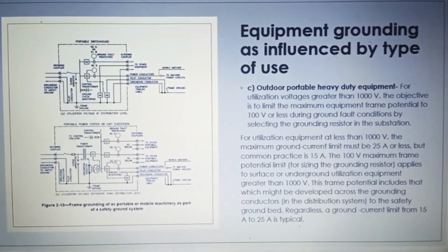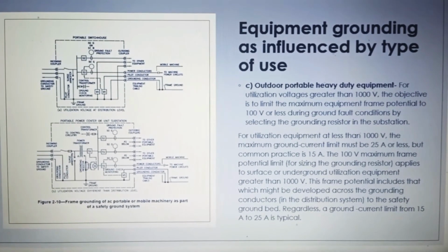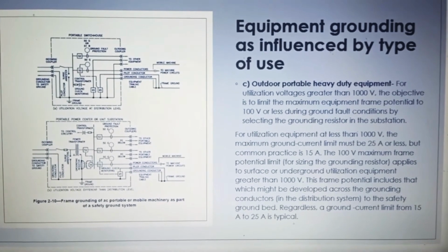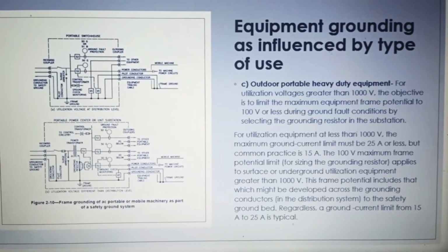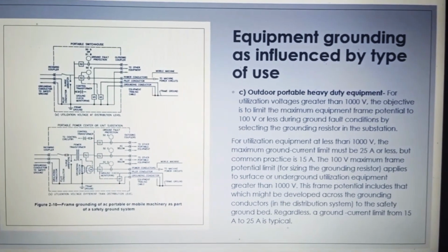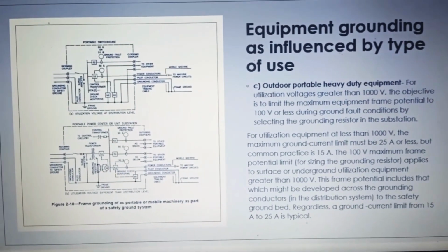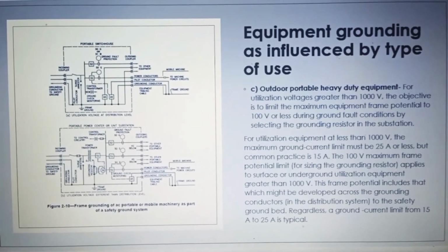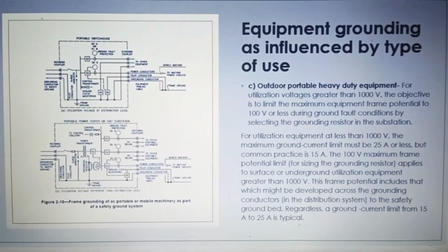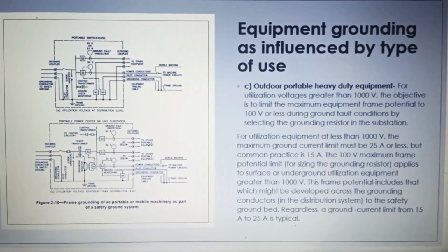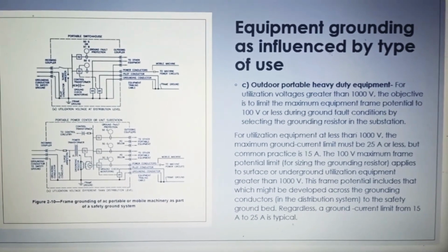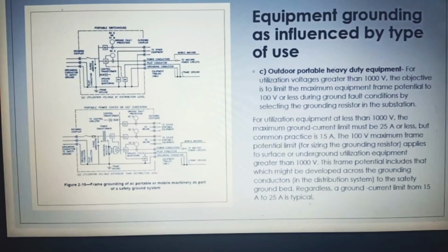Outdoor portable heavy-duty equipment. This area usually involves equipment such as power shovels, draglines, and mine installations. It presents one of the more difficult problems in avoiding dangerous electric shock voltage exposure. The mobility of the utilization equipment, and frequently of portable power equipment, precludes installation of a localized ground mat, such as would be employed at a fixed location. A safety ground system is utilized to ensure adequate grounding and personal safety. Both AC and DC equipment can be employed.